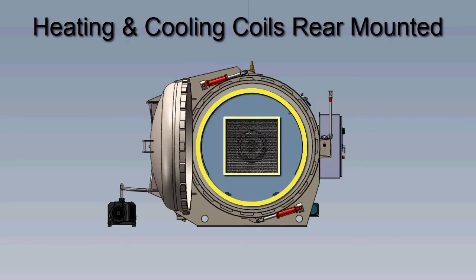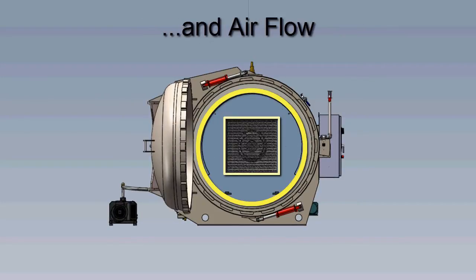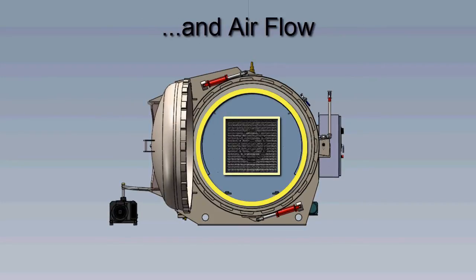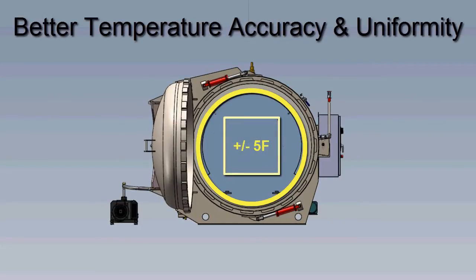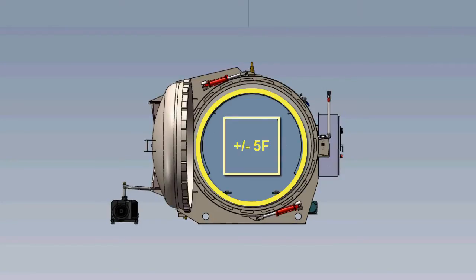Having these components in the rear of the chamber rather than the floor increases the amount of usable space within the autoclave and the airflow from the back flowing through the ductwork around the door and back through the center, helping provide temperature control accuracy and uniformity of plus or minus 5 degrees Fahrenheit.